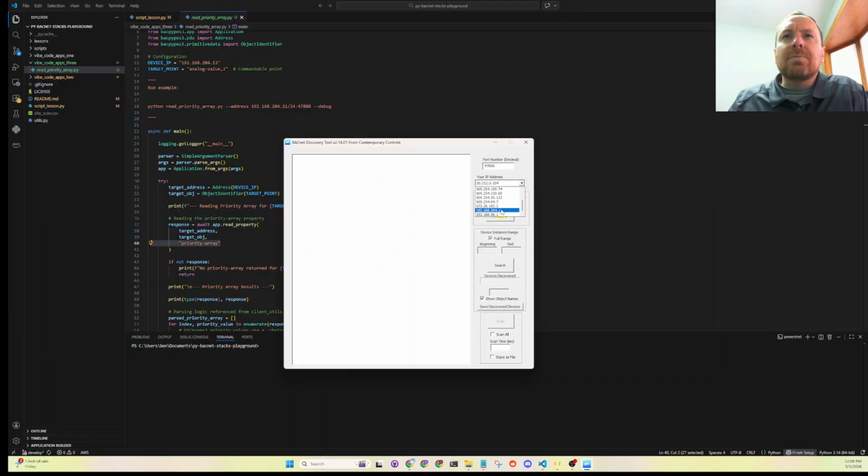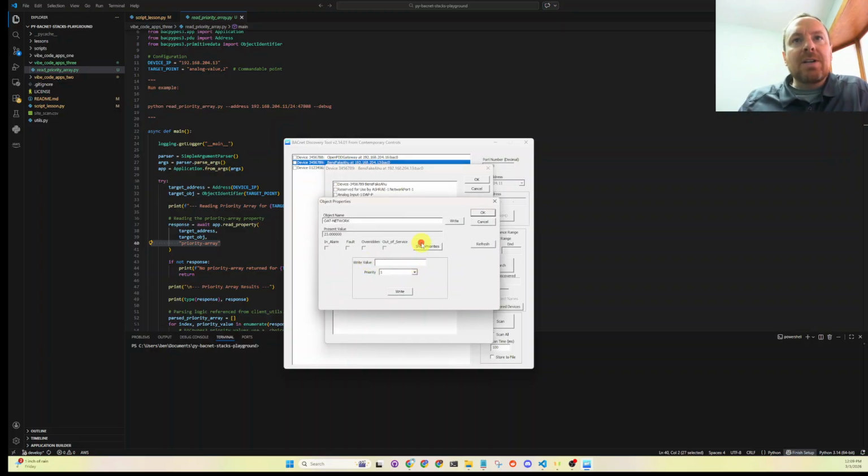So when we tested that out on the scan tool, I'm going to test it out, do my BACnet whois through the scan tool, which we've done a million times already. My test bench devices. And then I think we tested it out on analog value 3, networked outside air temperature sensor, then read our priority array through the tool. So wow, this thing has 3 different values written on the priority array. If you remember, that's what this will do right here. It'll read in, this device will give us this data in Python, and then we have to loop through it in some of the data structures we talked about. So this device has something on priority 10, priority 14, and a relinquished default of 60.